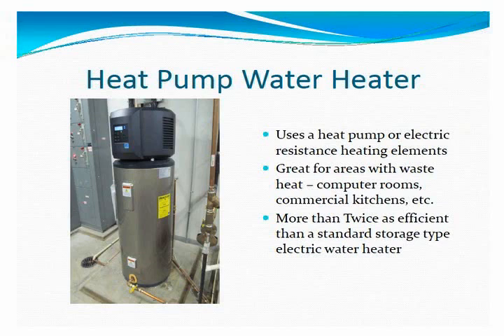We also have a heat pump water heater model. We're going to look at one of those in a moment in our own mechanical room here at our main office. This uses a heat pump or electric resistance heating elements. They're great for rooms that have waste heat, such as computer rooms, or as in the case of our mechanical room, where we have a lot of motors and other devices that put out heat. Commercial kitchens might also benefit from this type of water heater, and they are more than twice as efficient as a standard electric storage water heater tank.